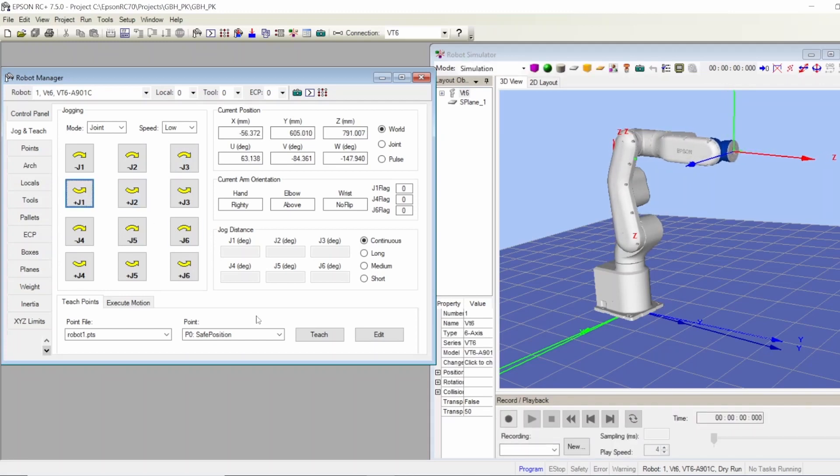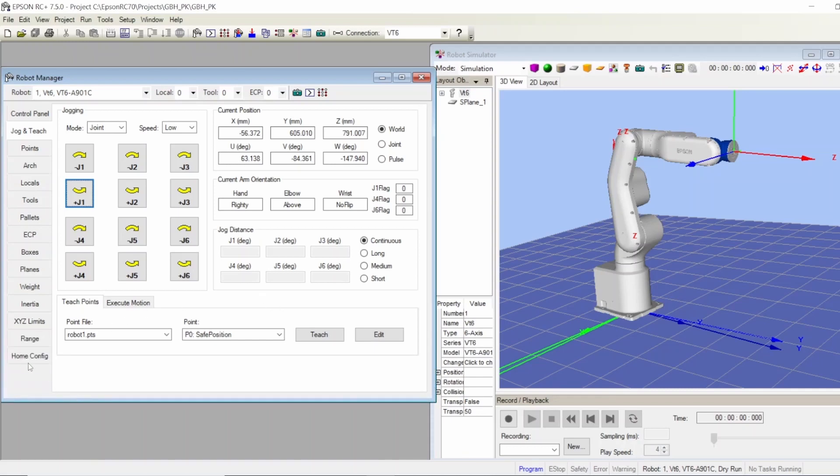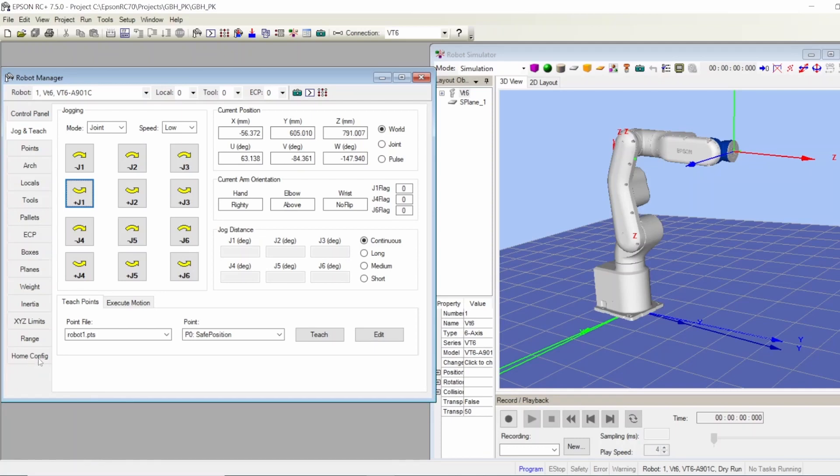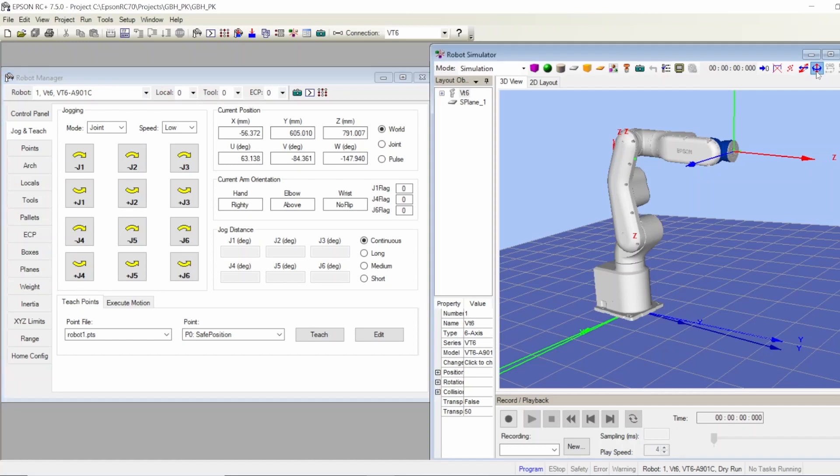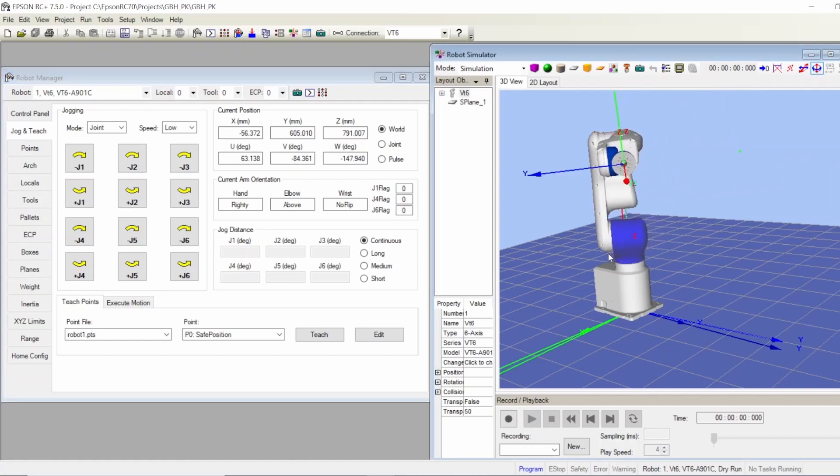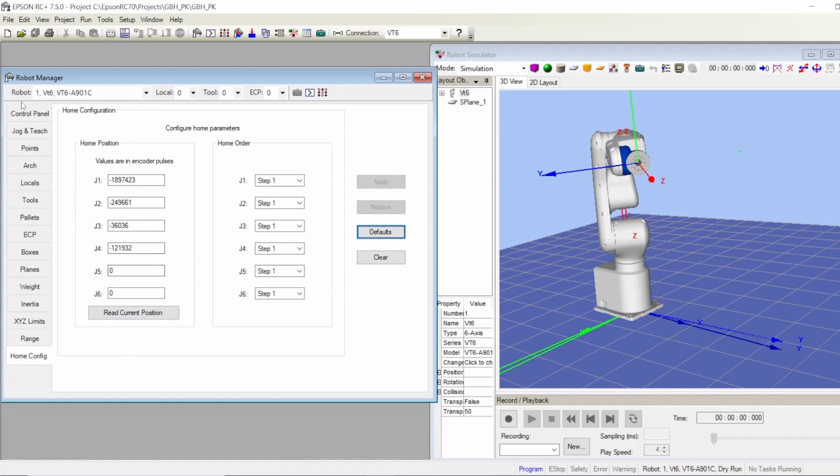The first thing you need to have is a home position for your robot. To do that, we expand this down. There is a home configuration all the way at the bottom. You press it and there is already a home assigned to it. But if you want to change your home position or if there was no home position, this is where you set it. Move it where you want it. Let's say this is your home position. You jog it, move it with this or this one. Then I go to the home configuration and read current position, change it to the current position, apply, and this is my home.